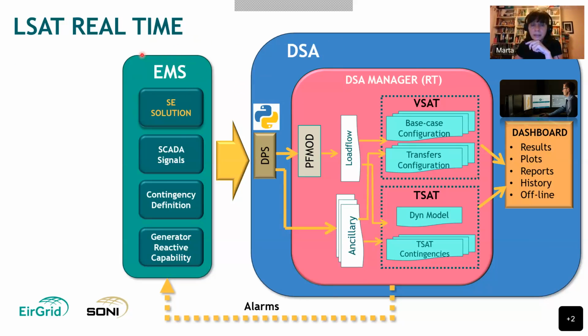In EMS, we start from the state estimator solution, which is conducted in EMS. There is an application that converts that solution from node breaker to bus branch format, and it's translated into PSS/E version 30 raw format. Then we also export SCADA signals, contingency definitions, and generator reactive capability curves. All those files are exported as flat files and exported into DSA.